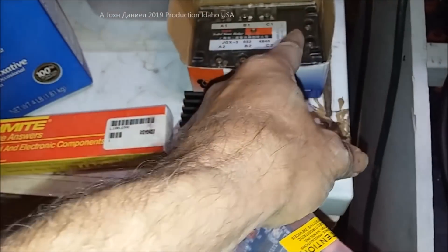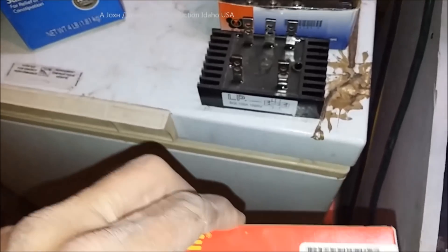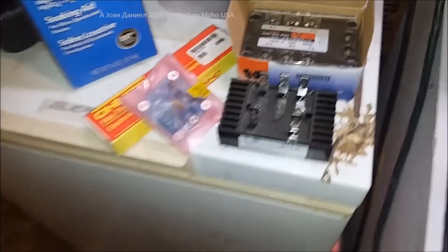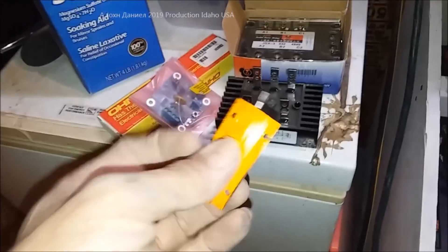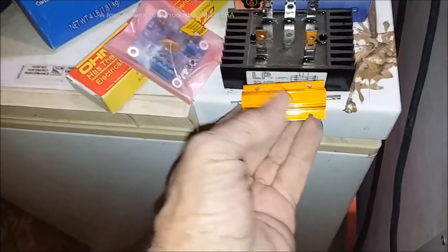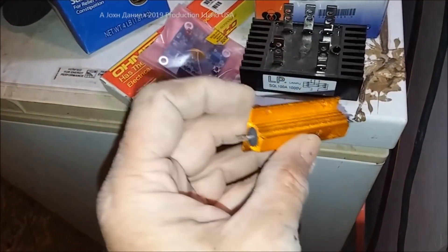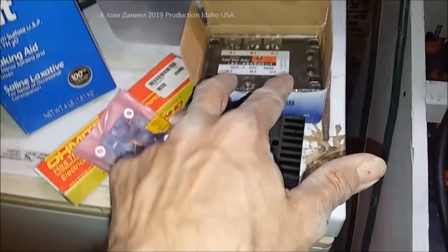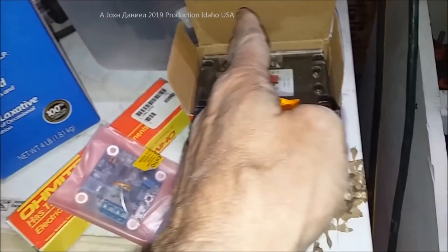When it makes contact, the solid-state relay sends the power to these points. It basically doesn't do a short-out as if crossing three wires together - it actually just feeds into a load. So the turbine can do that, and you can also apply a rectifier on this side. If I have a really out-of-control turbine, say a 48-volt in the Colorado Mountains - and we've installed six of these outside of Rifle, Colorado, so believe me it works very well - the turbine comes in, goes right back out all three phases. Over here you're basically not breaking the circuit, you're adding load to the circuit. When it hits 15 volts, kicks it on, feeds into the rectifier, turns it into DC voltage, goes through your resistors. The rectifier down at the battery bank doesn't affect it because that rectifier can only recognize voltage in one direction.